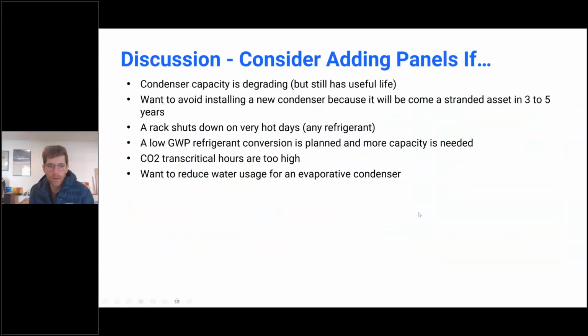So in terms of when we think it makes sense to have panels, we're not going to put panels on systems that don't have cooling loads throughout the year. Really, I didn't really mention this, but we want to focus on cooling systems that have loads not only during the day, but also at night, not only in the summer, but also in the winter. And that's because the panels can reject heat all the time. And that's how we can get more energy savings in our panels than say solar panels. And that's really driven by the fact that we can cool at night, and you can only cool at night if you have a load at night. And so that's why having a refrigeration system or high occupancy building where cooling is persistent, or a data center is the focus in these case studies. And so they're going to make sense when you have condensers that are degraded, underperforming, but still have some useful life.